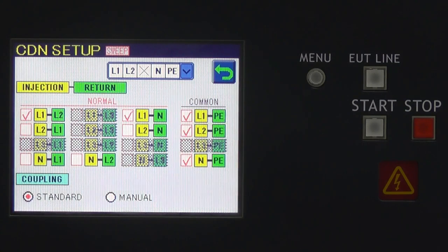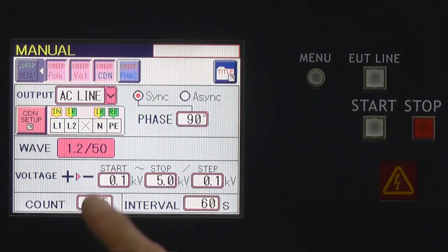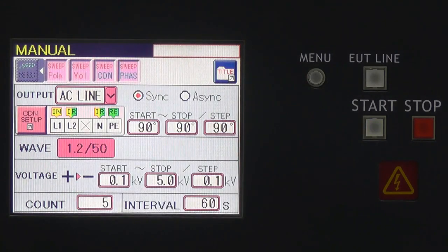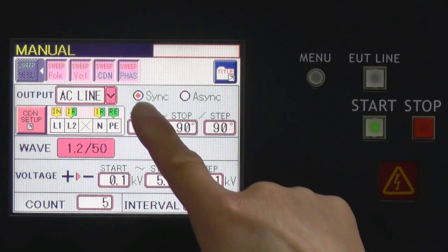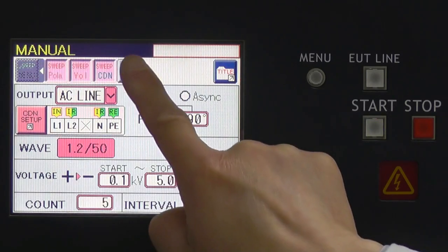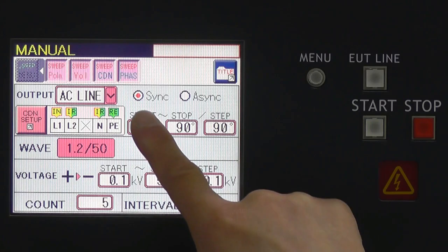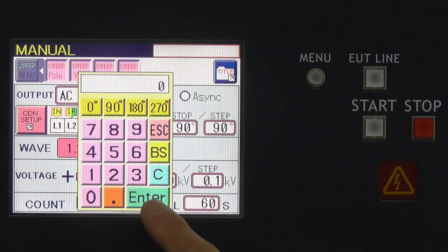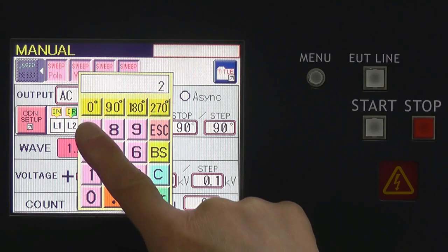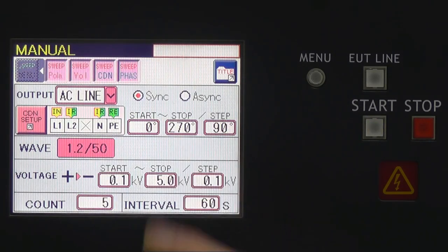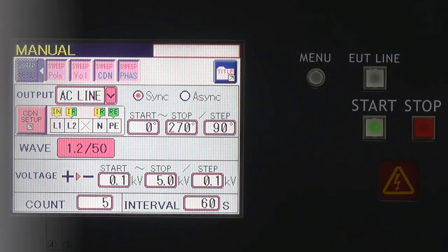Okay, let's go back to standard mode, and next you might want to set the phase either synchronized or unsynchronized. Let's say we start the phase from 0 degrees to 270 degrees here, at 90 degrees per step. And now, with all the conditions we have set, the test will run automatically through the conditions we've just set.